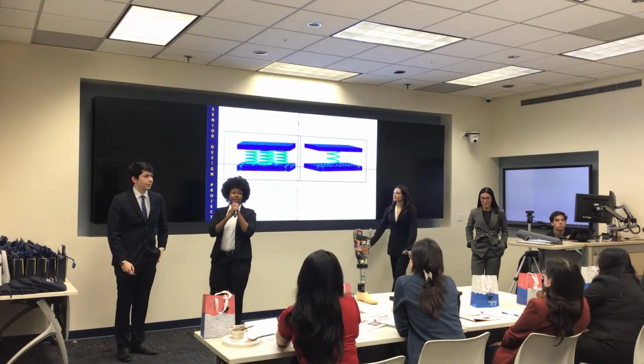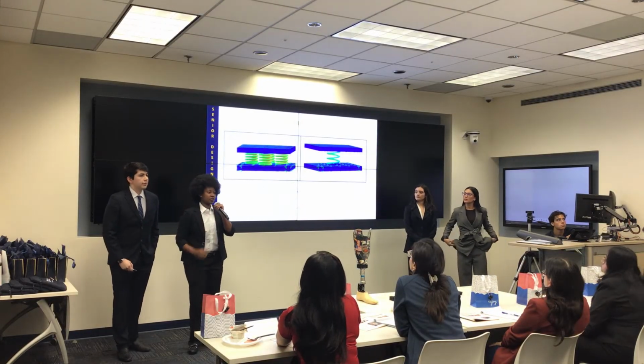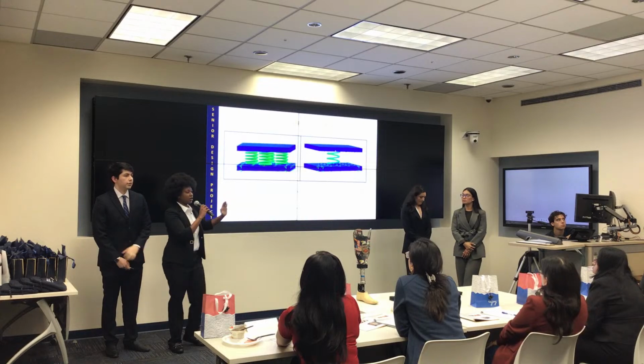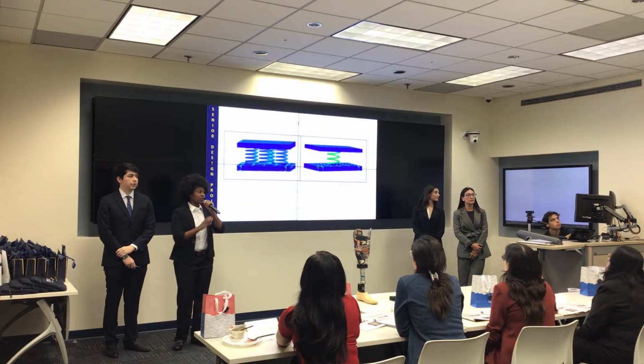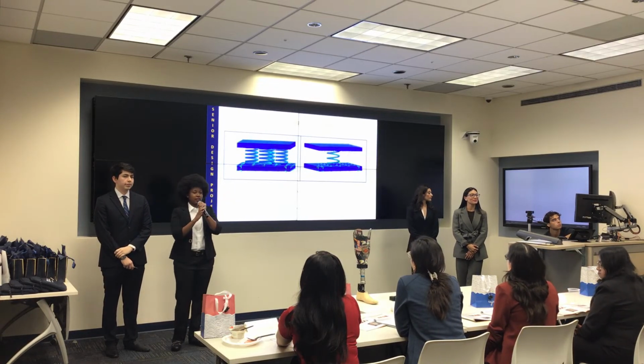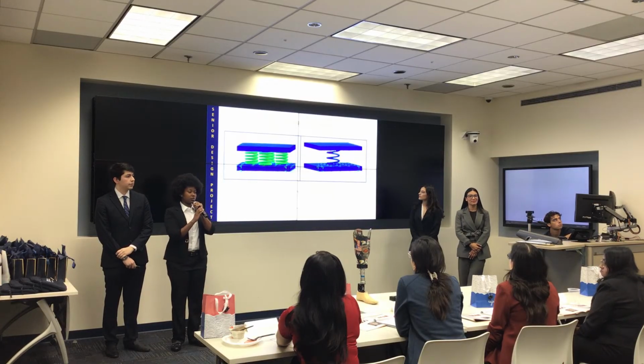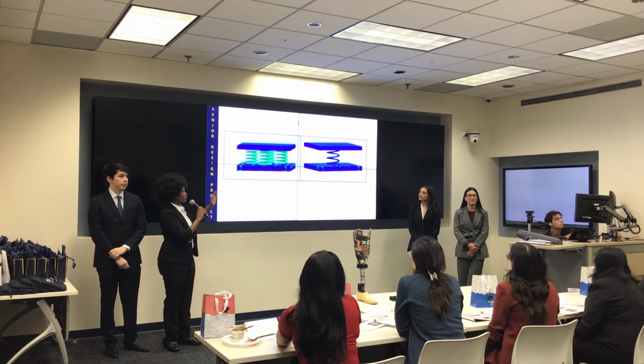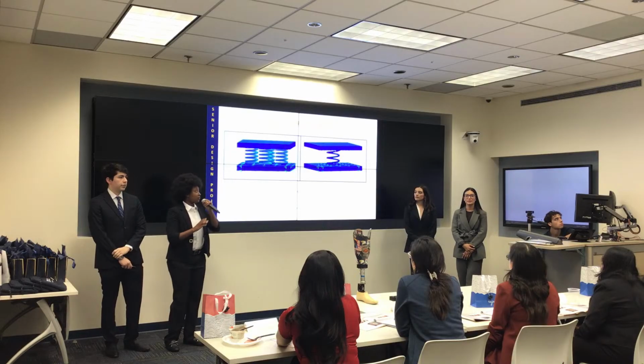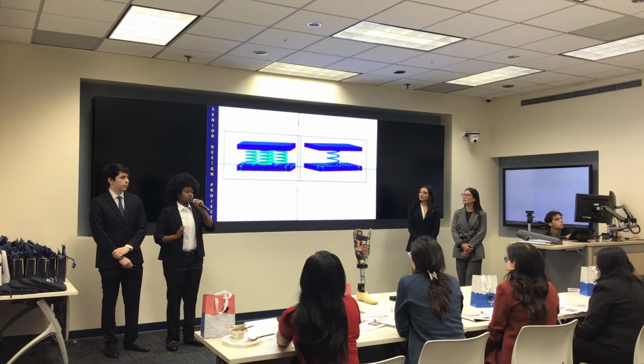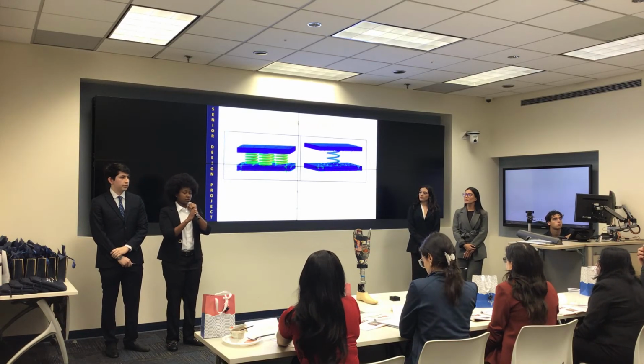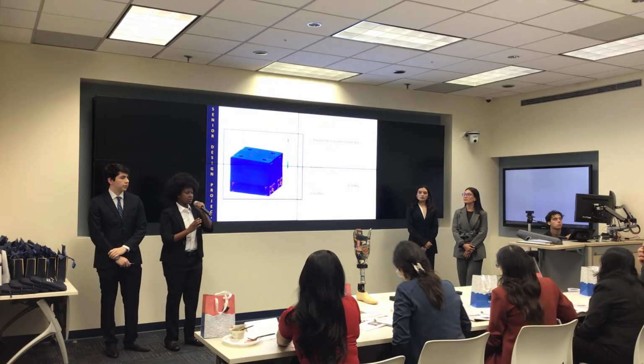Thank you. So we conducted a pre-design study where we took a look at 4 springs versus 1 spring after looking at several configurations. Ultimately, as per the ISO 10328, we must meet 1,000,000 cycles, and fortunately the 4 springs were able to pass that, but unfortunately the 1 spring was not able to pass that. So we decided upon the 4 springs. Next, on to the stress analysis.